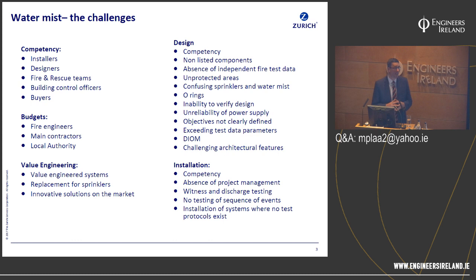And we also have another challenge around O-rings. It's a hard lesson that the sprinkler industry learned a few years ago about O-rings in sprinklers, where elevated pressures were required for the sprinkler heads to work. When you send them away to a test lab to be tested, they will generally fail and may require 6 or 7 bar to release the seating. Well, the water mist industry and some manufacturers are now repeating the mistakes of old and selling O-rings within their heads. So the lesson hasn't been learned. So that's really an important one.